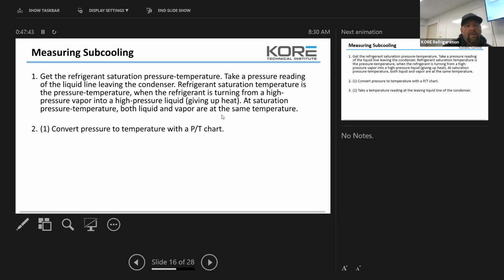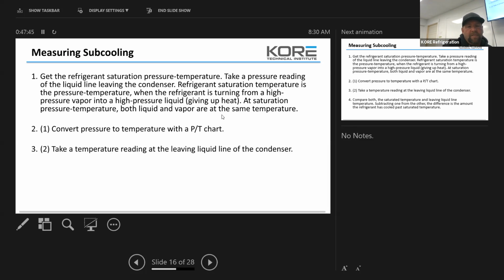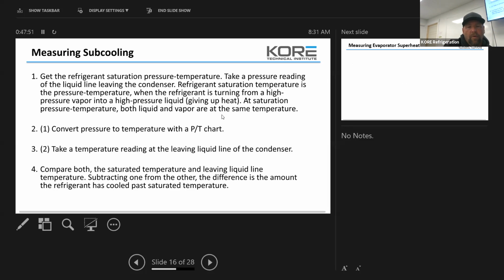So convert pressure to temperature with a PT chart. Take temperature reading at the leaving liquid line of the condenser. Compare both at saturated temperature and leaving liquid line temperatures. Subtracting one from the other gives the difference, the amount the refrigerant has cooled past the saturation temperature.